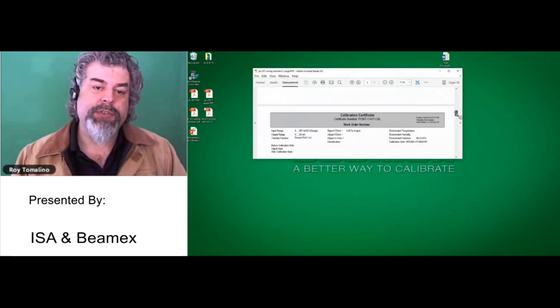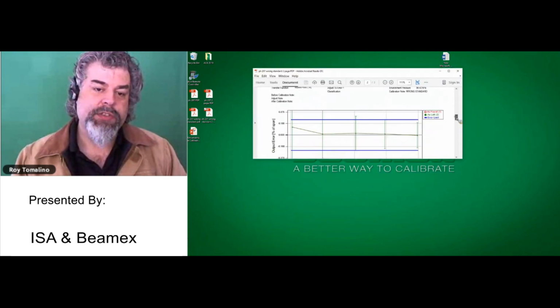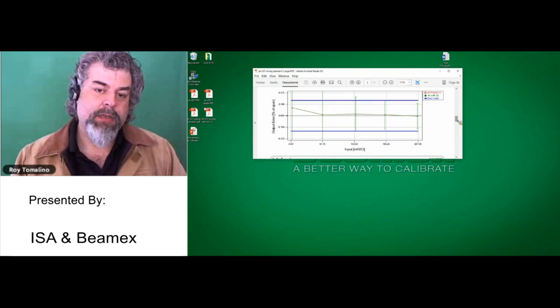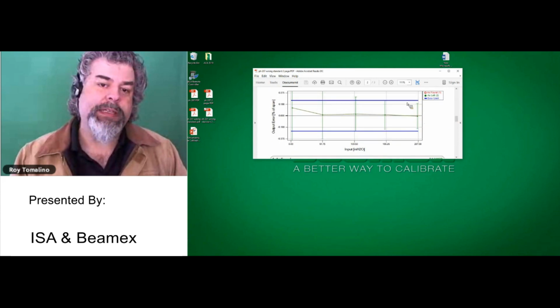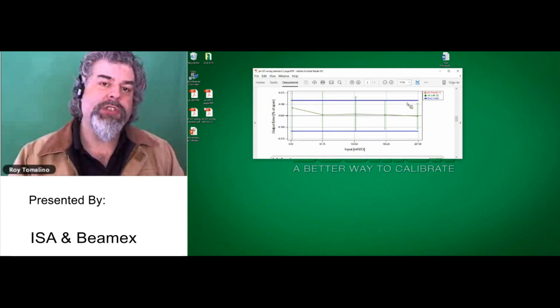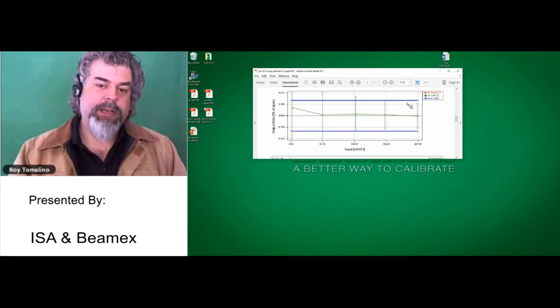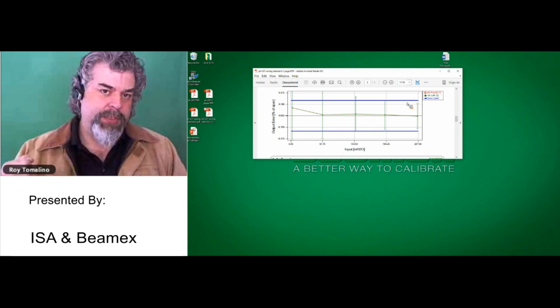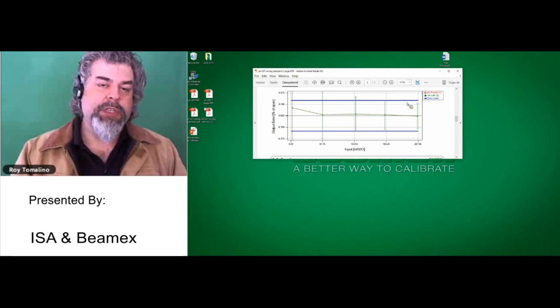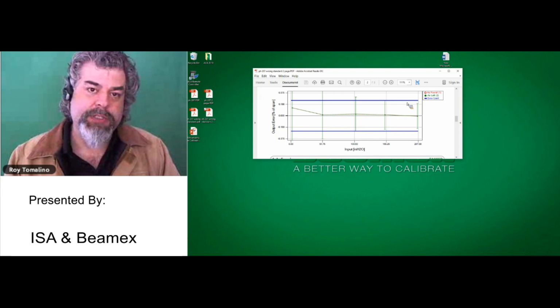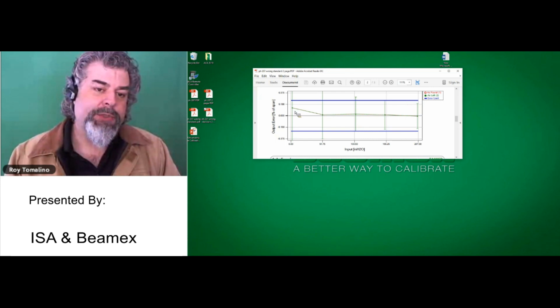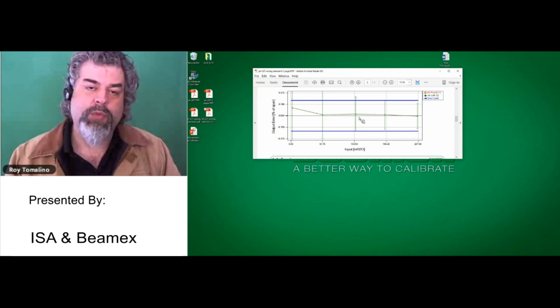This is my calibration certificate, and I want you to see the graph. The blue lines, again, represent my tolerance, and any calibration software worth its salt should automatically calculate your uncertainty of the test standard that you're using. And the software that I'm using here is calculating exactly that. It's calculating the uncertainty and the expanded uncertainty. So if we look at our first test point, our second, let's go to our third one.